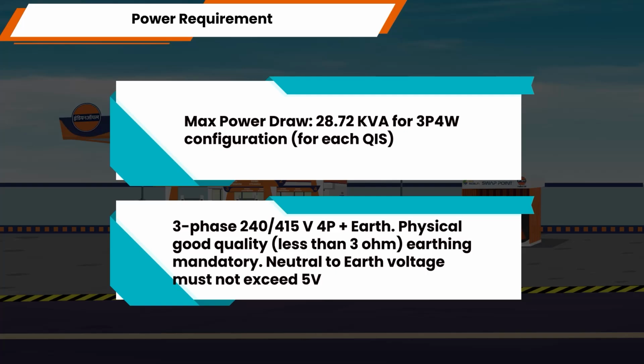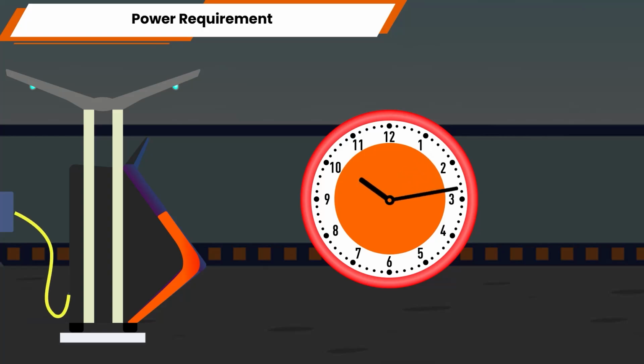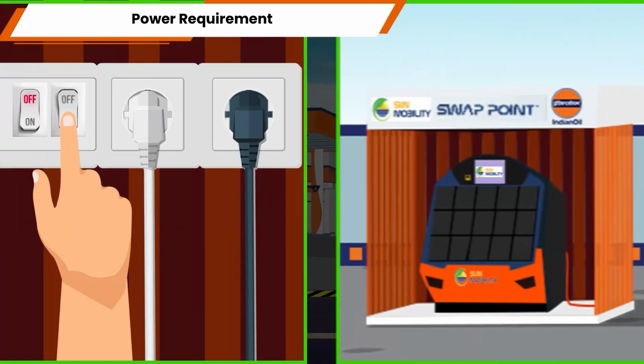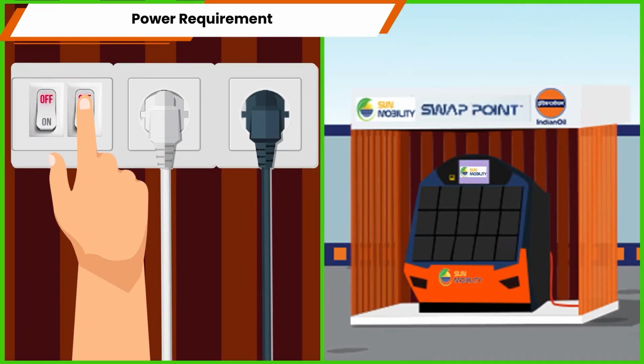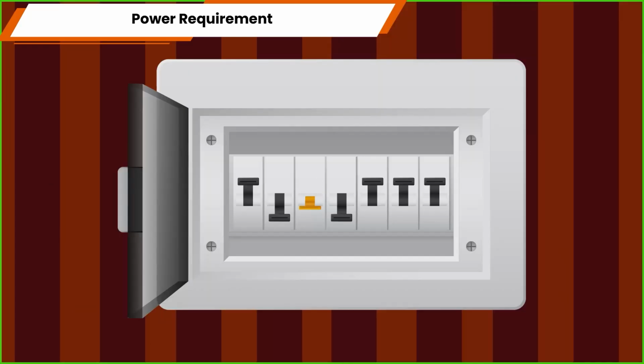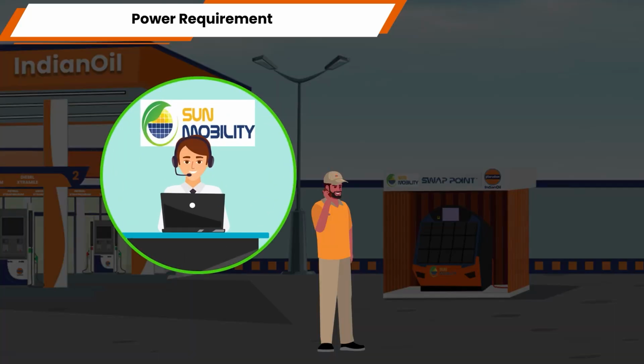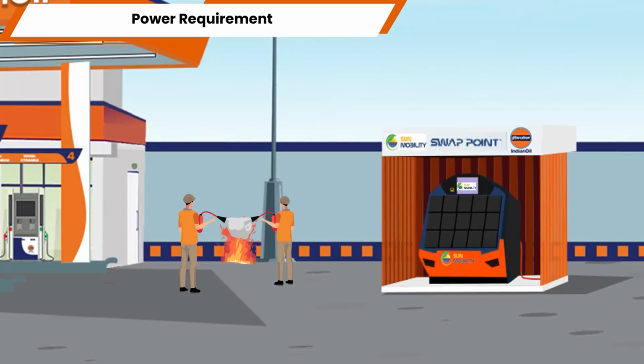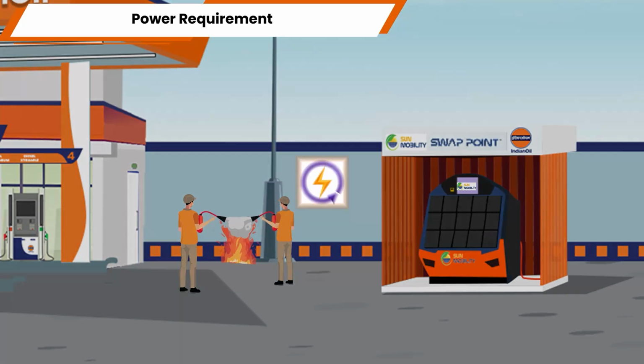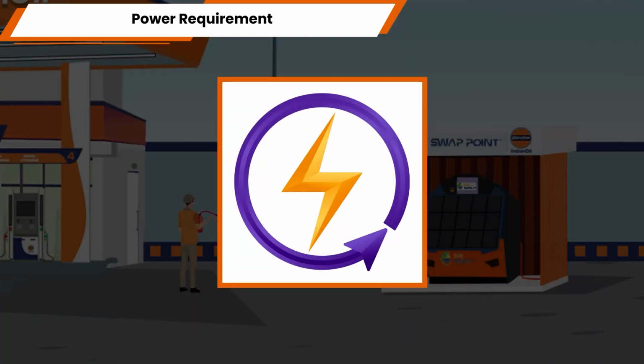Neutral to earth voltage must not exceed 5 volts. 24 by 7 power supply required. Maximum supported power outage time 1 hour and 15 minutes. System should not be shut down for more than 3 days in a row. To power off, contact QIS representative. In case of an emergency, the system power to be cut off, which will lead to QIS shutting down automatically and recovering gracefully upon AC power recovery.